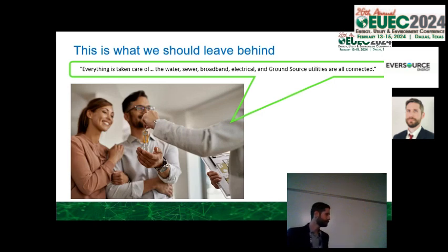To give one more example, in Whisper Valley during Superstorm Uri, when the outside temperature went down to, what was it, like 10 degrees here? It was zero-ish. So way below what anybody's expecting here. The water in that horizontal ground loop lost 1 degree of temperature. So that's it. It's fine. The heat pump will continue to work extraordinarily happily with the temperature going just 1 degree difference. Nothing.